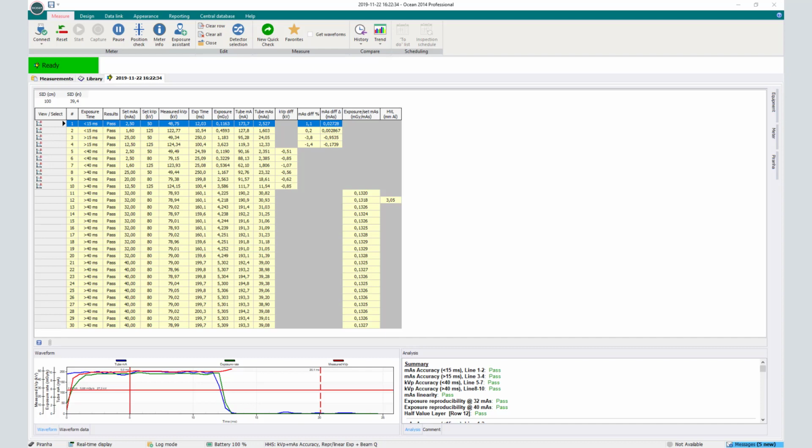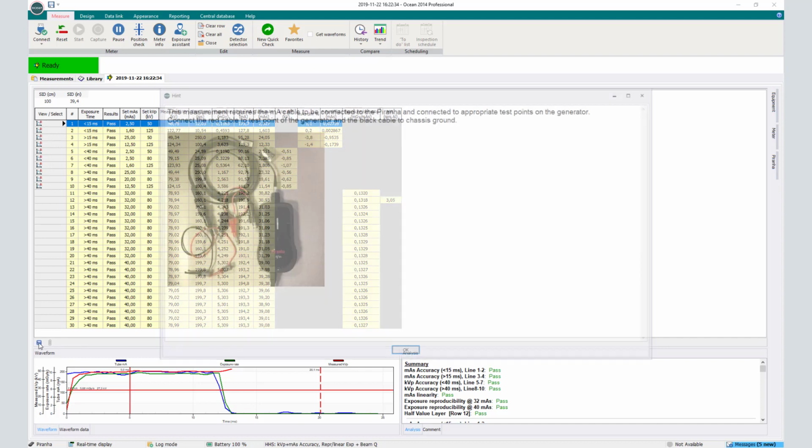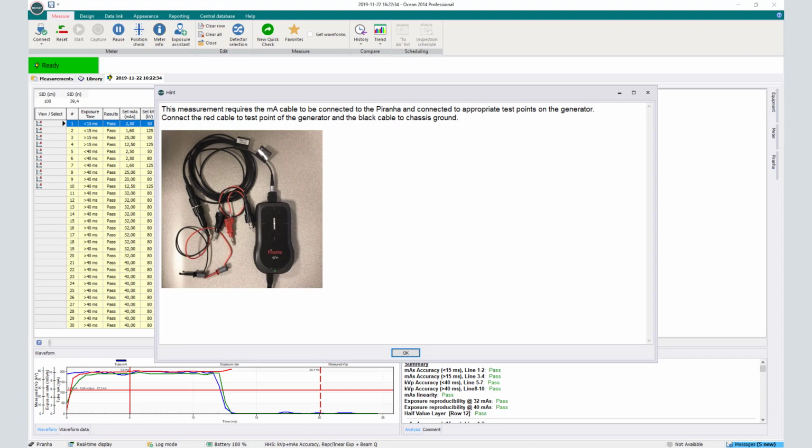A template also offers the possibility to present the user with support information, like what tools and probes could be used, or photos or drawings or circuit diagrams showing the measurement setup and other relevant info to increase the chance that the user performs the measurements in the same way. If that is achieved, data will correlate and thus improve data quality.